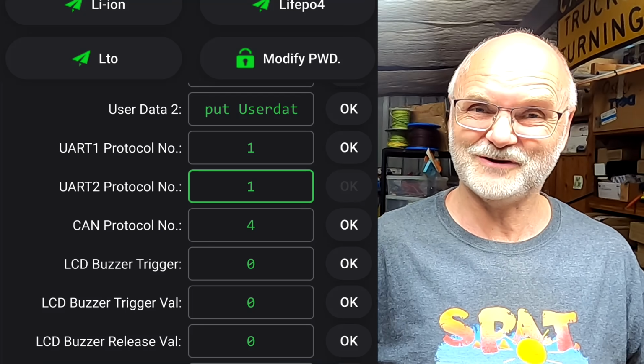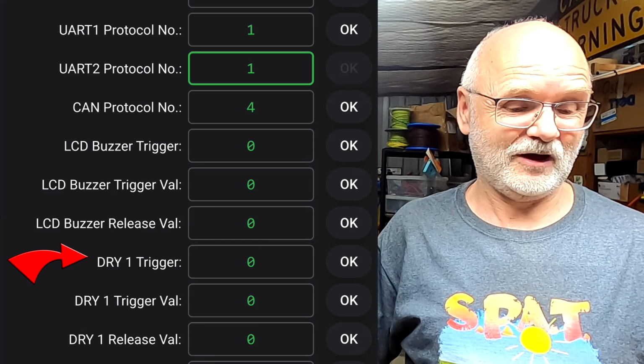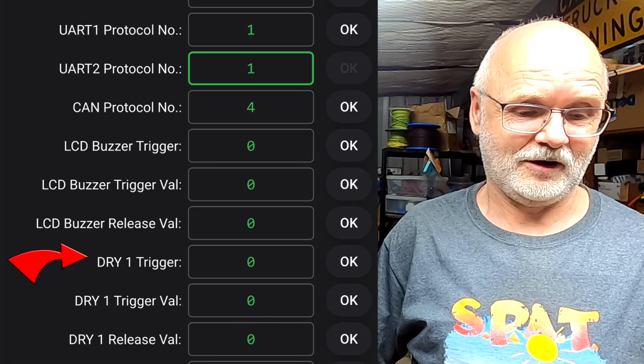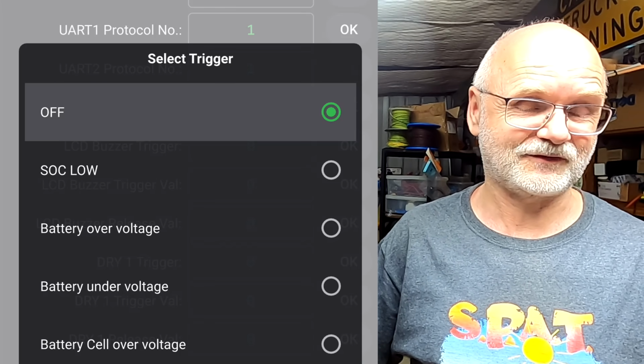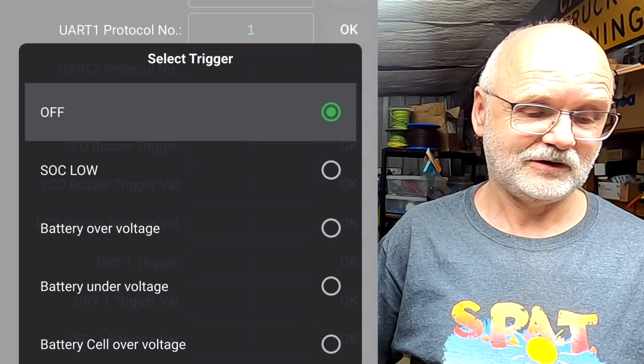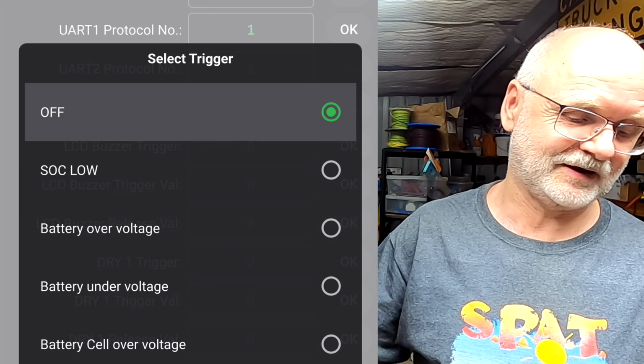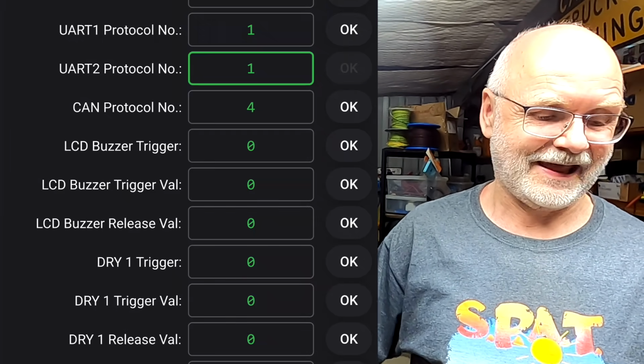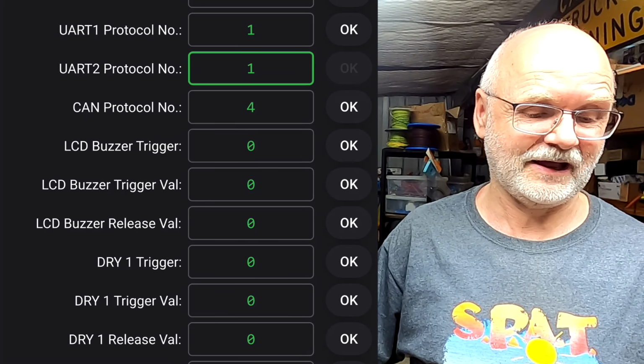So pretty cool, right? But wait, there's more. We also have a dry contact trigger. Clicking on this gives us similar trigger points: low state of charge, battery over voltage, under voltage, current, temperatures. And here too we have a trigger and a release value.